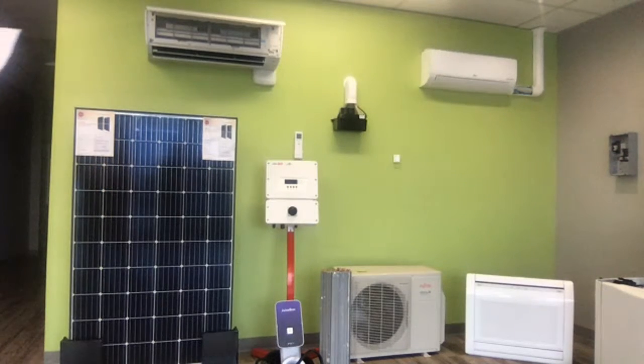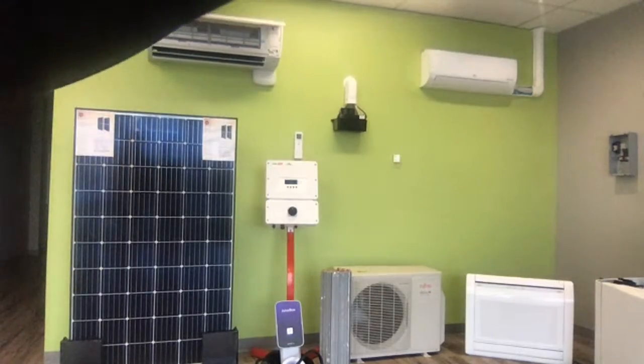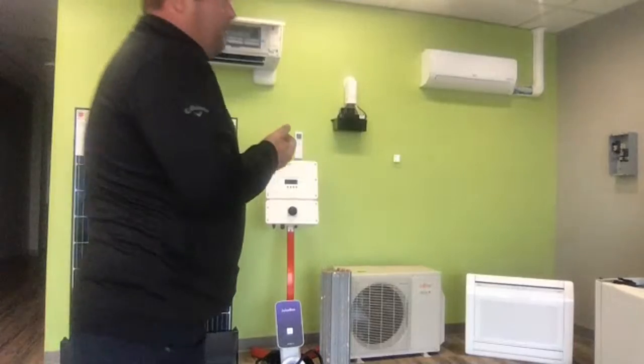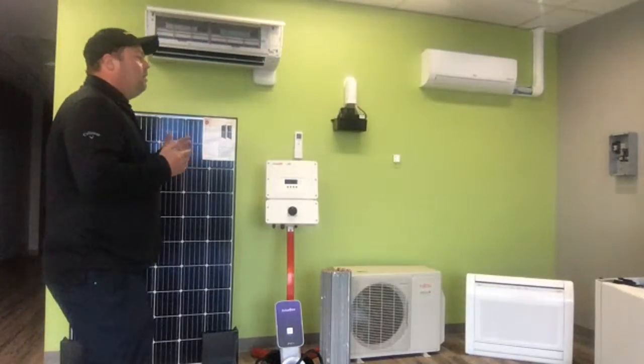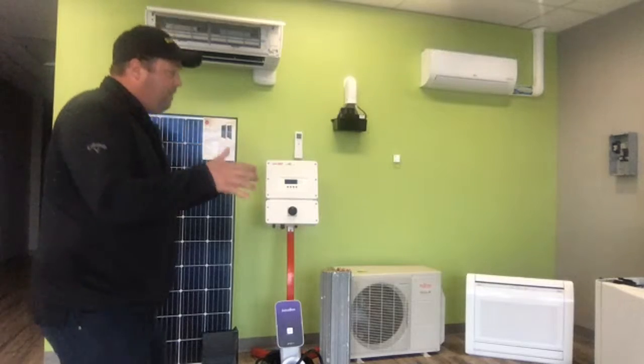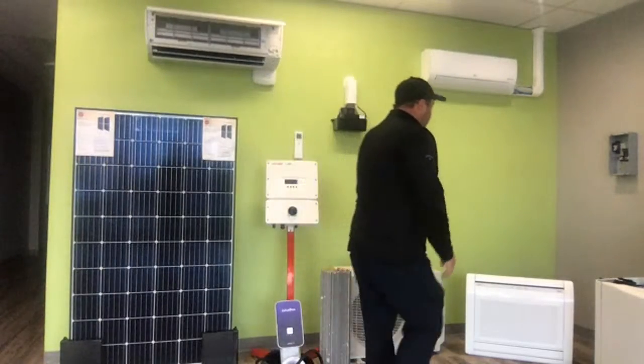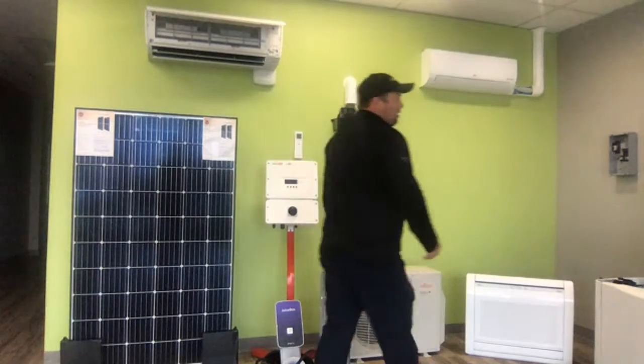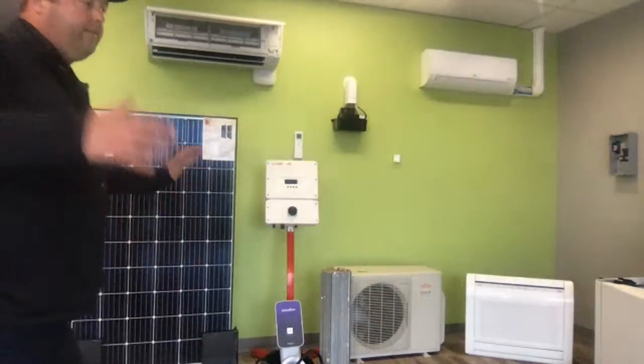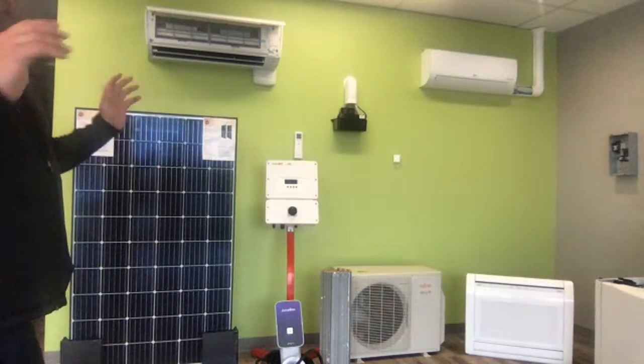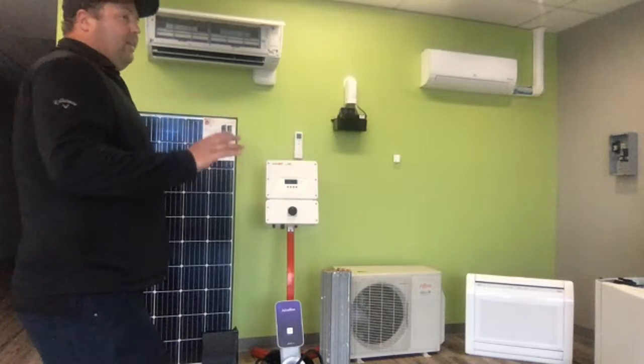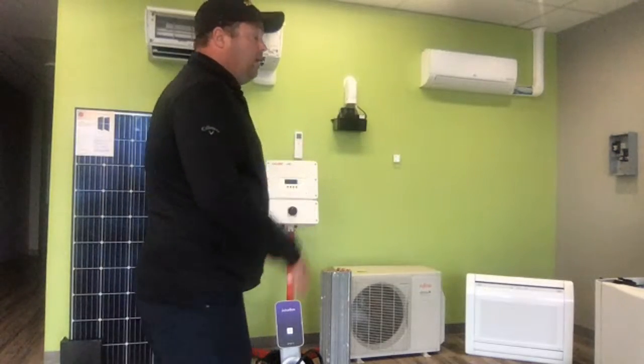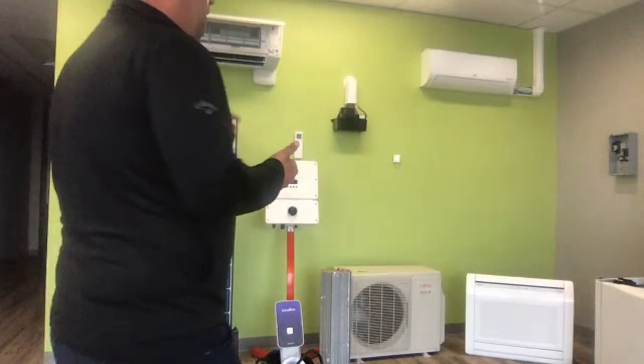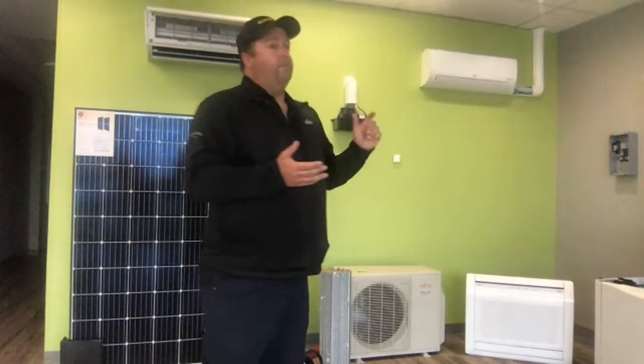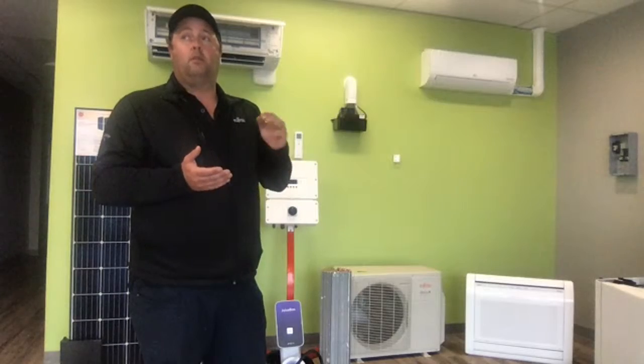Cost of ETS. So when you're talking about ETS, we have to pull a permit. We put a timer on the hot water tank. It has to be appropriately sized for the space. You can't buy a little dinky one the size of this and expect them to pass you on time of day meter. I know the guy there, he won't do it. You have to have an appropriate ETS in order to fill the space. A 408, which is their number one seller, which is kind of the minimum we're generally looking for if we're putting one in. You're looking at about $2,400, I think, plus tax when you have your ETS wired in, with permits, inspection, and timer.